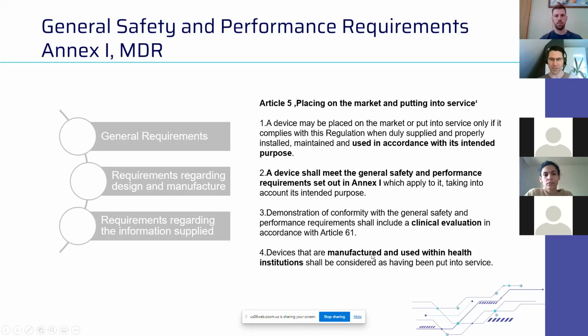Devices that are manufactured and used within health institutions shall be considered as having been put into service. If I am liaising as a technology provider with a hospital, and that hospital uses my medical devices, they fall under this regulation. The very moment the hospital sells those devices or puts them somewhere else in use, let's say at another location, it's considered to be placed on the market. At that time, CE marking is compulsory.